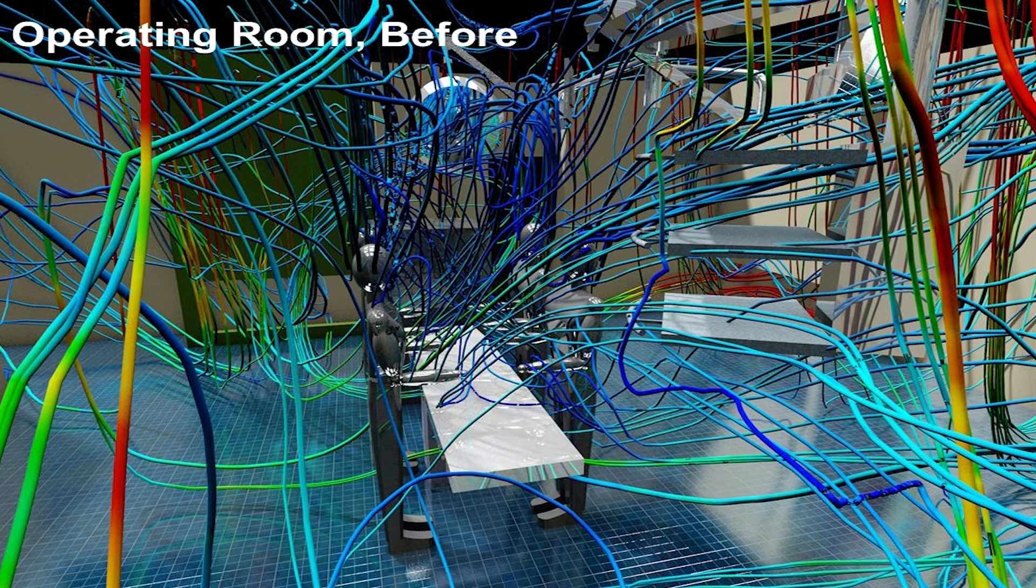We're looking at again tracers that were set up in key points in the room to make sure that we knew where all of the contaminations would go. And before any of the modifications were done you can see it was a mess. So contaminants, particles, they were all over the place. There was no real clear pathway for the exhaust to go.